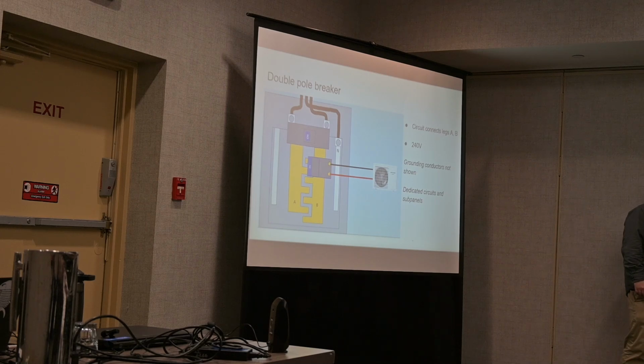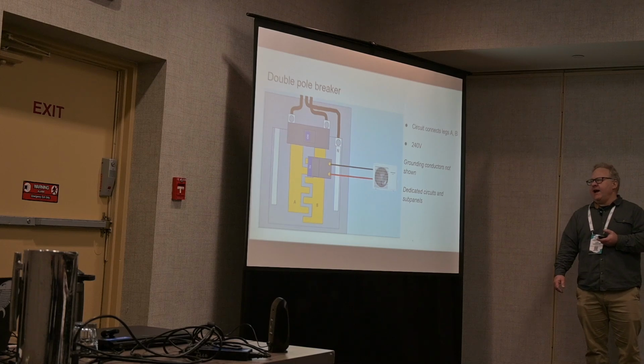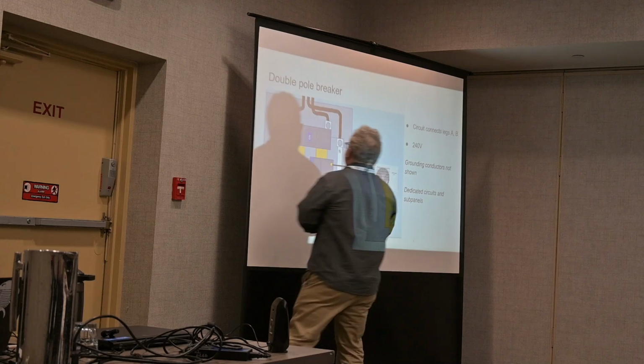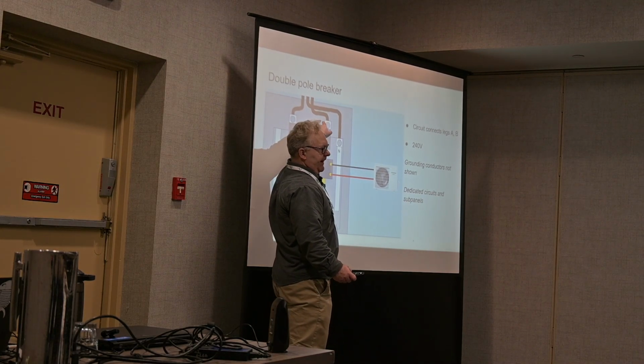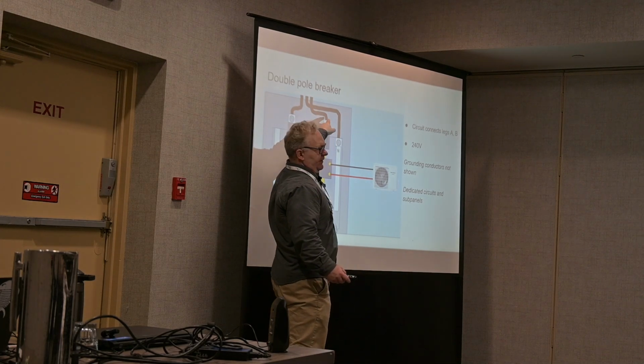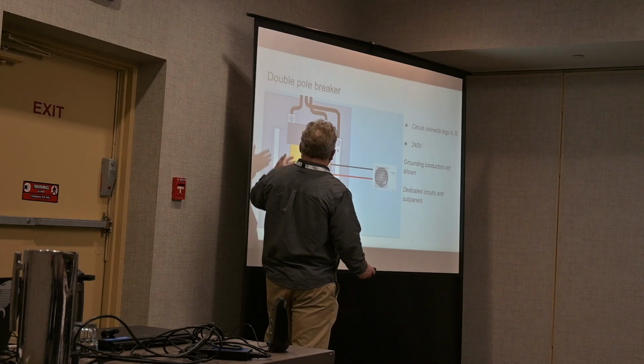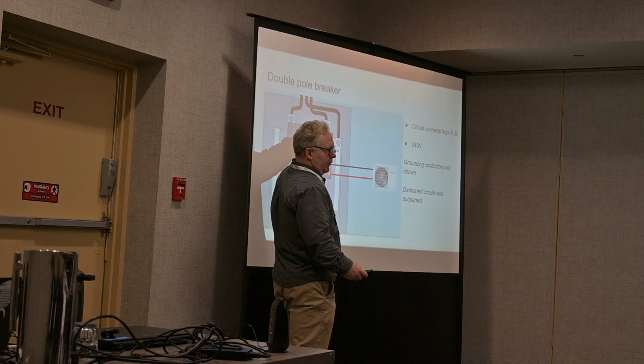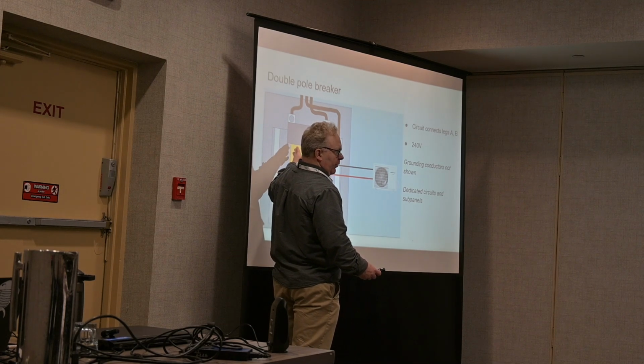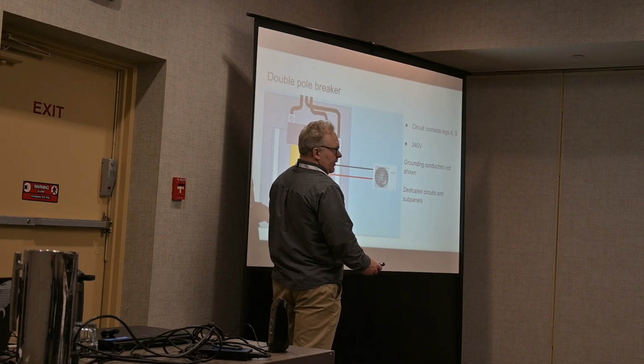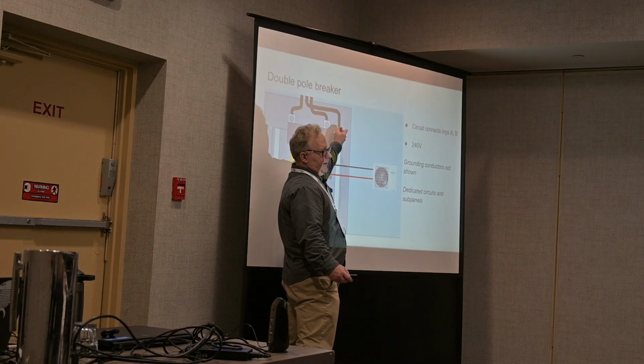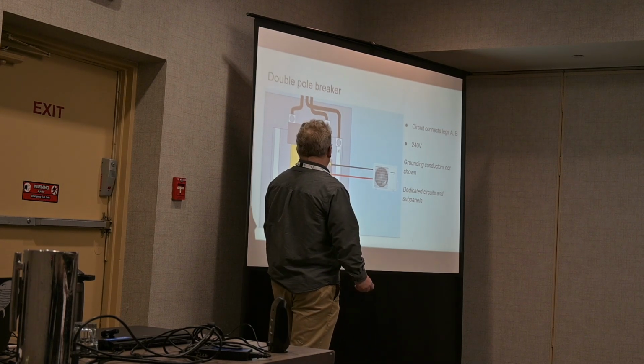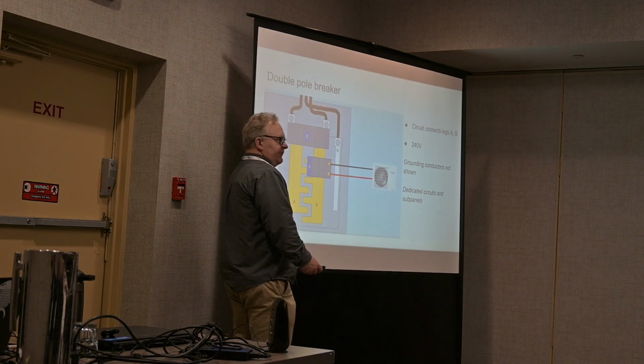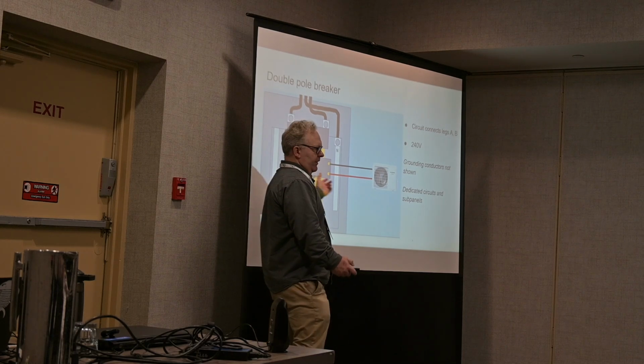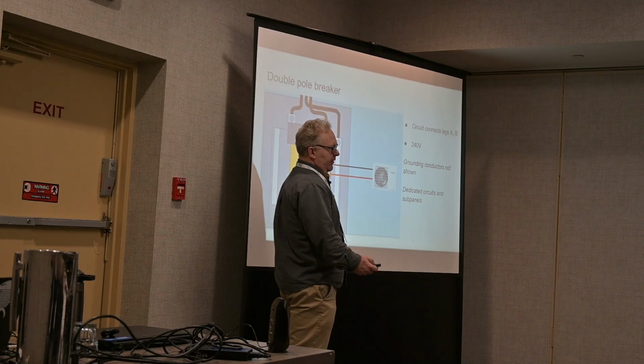When we talk about balancing the legs, is that just balancing the A and B leg for the box, or isn't that such a thing? Yeah, that's a good question. Each of these hot conductors has a rating. If this is a 100 amp panel, each of these live conductors is rated for 100 amps. And if we connect all our loads to one leg of power, we're going to have more flowing through one leg than the other. And also, those loads won't cancel each other out through that neutral. So that's something to be aware of. It's something that honestly I've just not run into a lot. But in general, you want to make sure that your single pole loads are evenly distributed across the two legs.